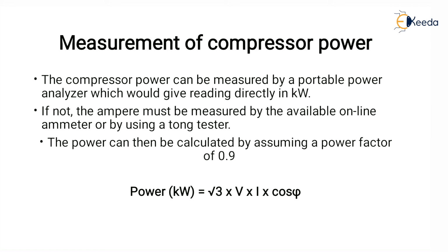Next is measurement of compressor power. The compressor power can be measured by the portable power analyzer, which would directly give out the reading in kW. But if not, then the ampere must be measured by using an online ammeter or by using a tong tester. And the power can be calculated by assuming the power factor of 0.9. So the formula is power P equals root 3 V I cos phi.